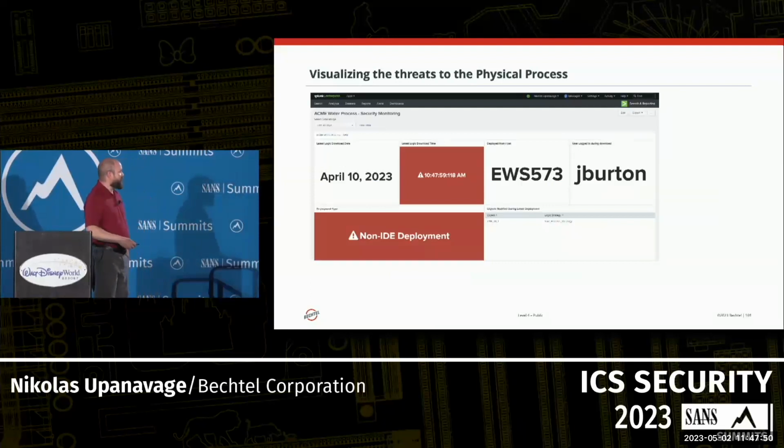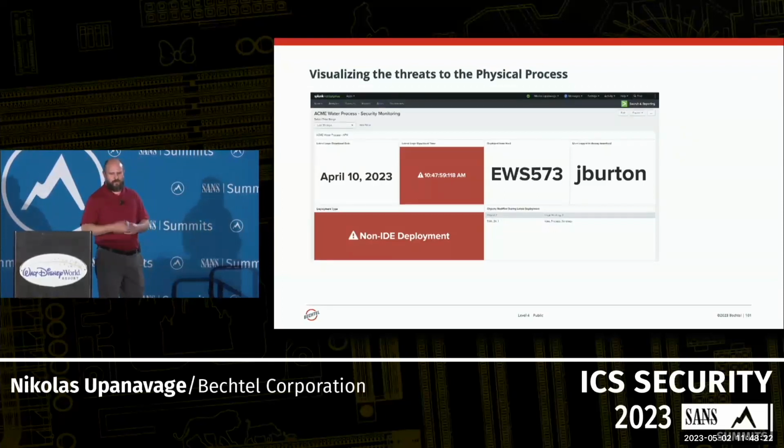Looking at how to visualize this, some of the key things we wanted to think about: we're downloading logic changes, so when would these logic changes usually happen? So we created a logic or maintenance window, a set of hours during a day, normal hours where an engineer and operator could push logic to the controllers. That's one part of it.